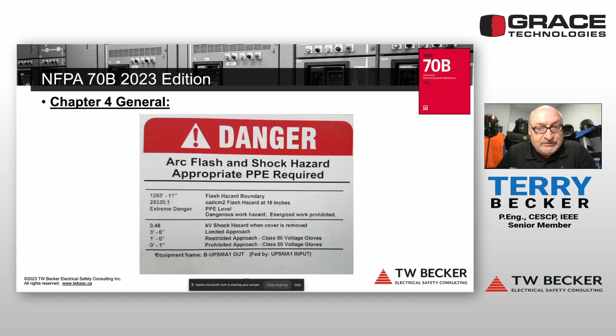You might find some labels that are interesting. This was a label—I can't remember where I got this from, it's been a while back—but it reads 25,330.1 calories per centimeter squared. This is another thing your inspections might catch, related to the arc flash studies. The label doesn't make any sense.